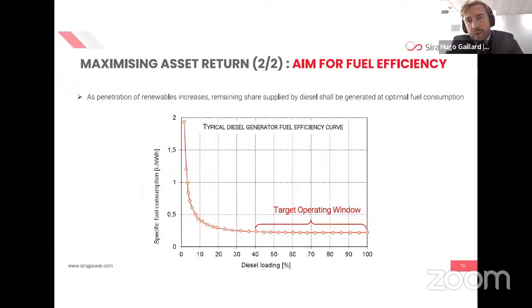Now, the second lever is to ensure that the remainder of the power is generated at an optimal fuel efficiency. As we mentioned before, we are using hybrid solutions, which means that part of the energy mix comes from solar, but the remaining part will come from fossil fuels. Now, it is key that this remainder is generated at an optimal fuel efficiency. And as you can see here on this typical diesel generator fuel efficiency curve, a diesel generator will run efficiently whenever its loading is, let's say, above 40%. So in a window, what we call the target operating window, where we want to operate the generators.